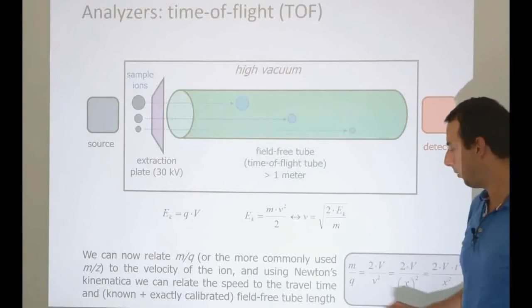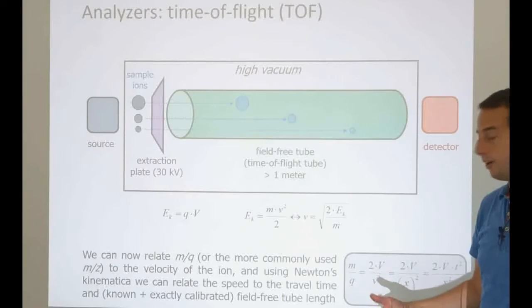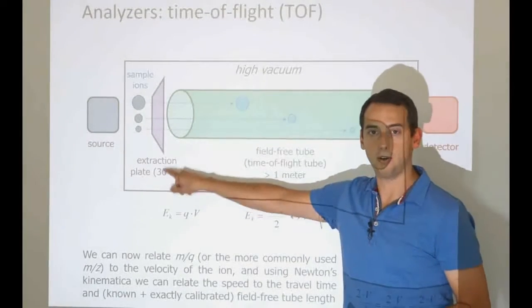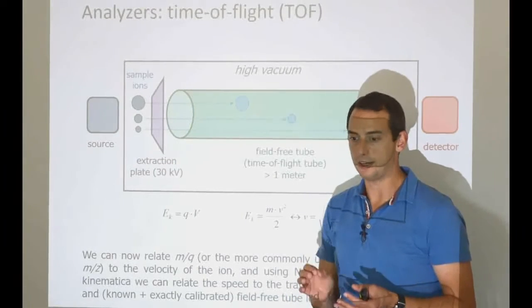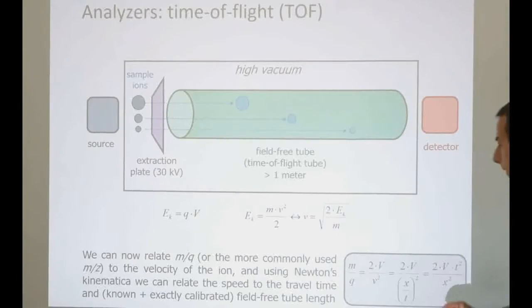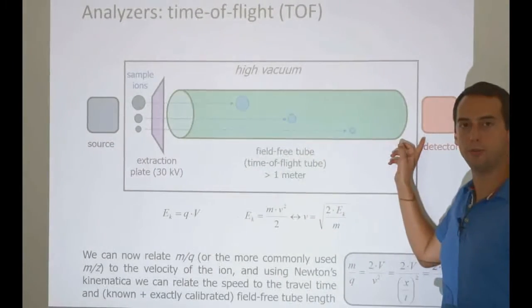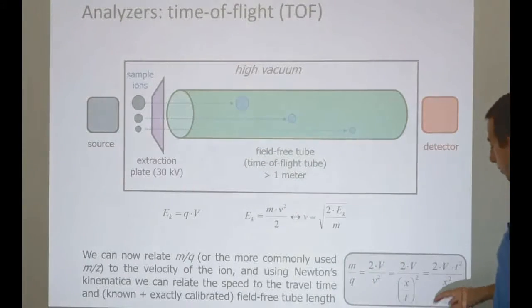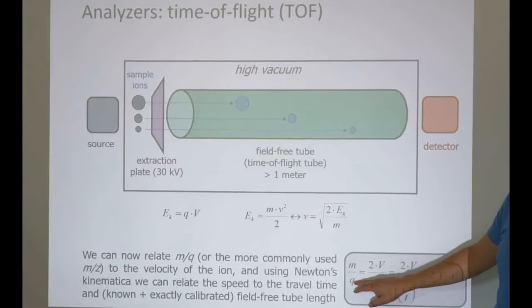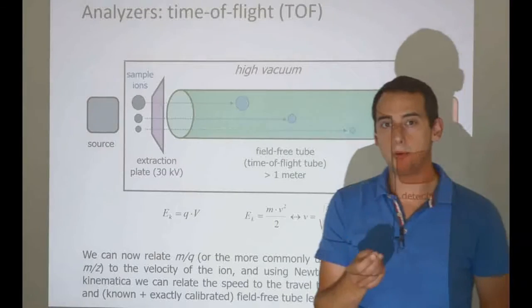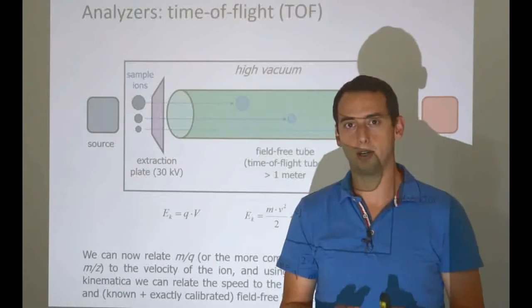Let's see what we know. We do not know mass and we do not know charge — those are what we're trying to find out. We do know the factor of 2, we know V (the voltage), because that's what we told the instrument to apply on the extraction plate — it's very tightly regulated. We also know the time traveled because that's our stopwatch built into the mass spectrometer, and we know the distance traveled because we know how long the tube is. So we can resolve the mass over charge, but we cannot distinguish between different charge states of different ions. We always measure mass over charge together, never mass alone or charge alone. And this is a really big limitation.